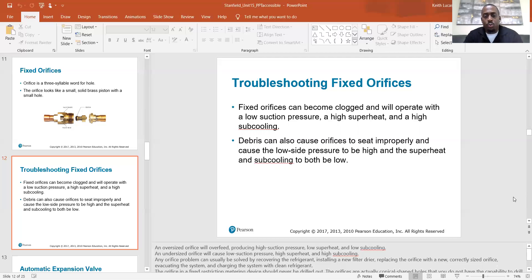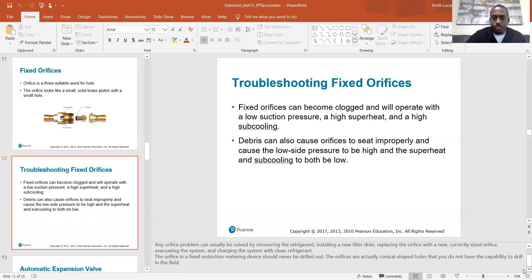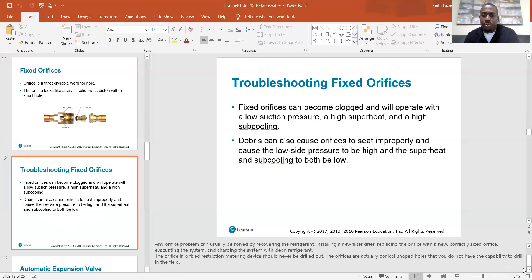An oversized orifice will overfeed, producing high suction pressure, low superheat, and low subcooling. An undersized orifice causes low suction pressure, high superheat, and high subcooling. Any orifice problem can usually be solved by recovering the refrigerant, installing a new filter dryer, replacing the orifice with a correctly sized one, evacuating the system, and recharging with clean refrigerant.